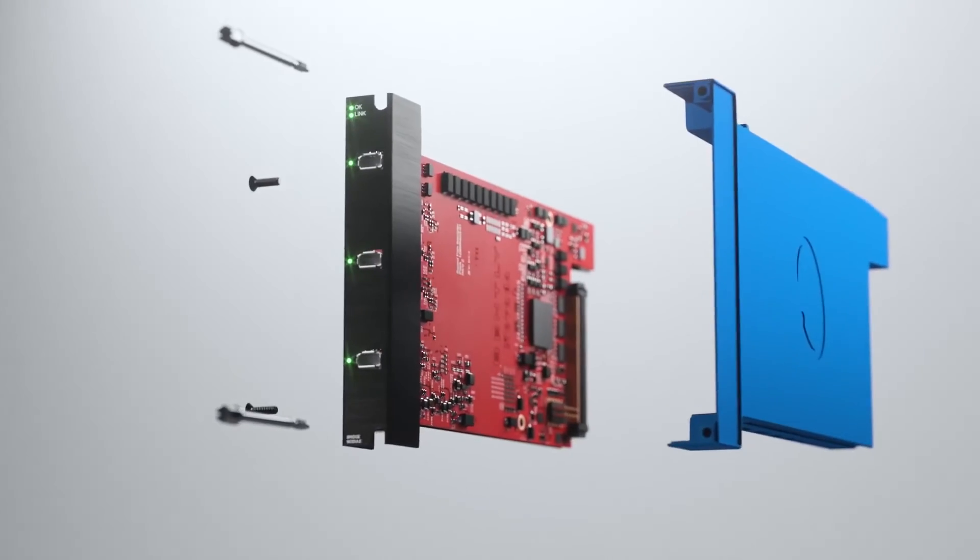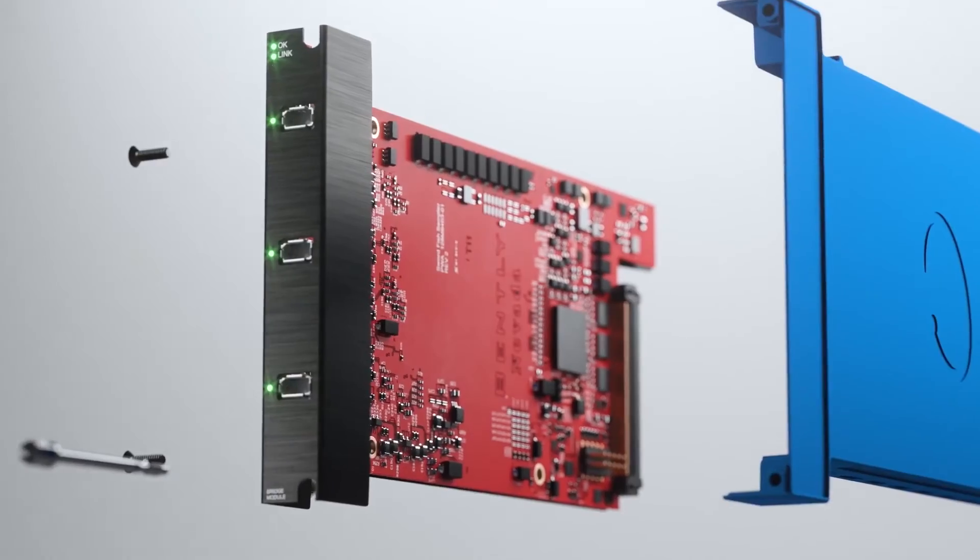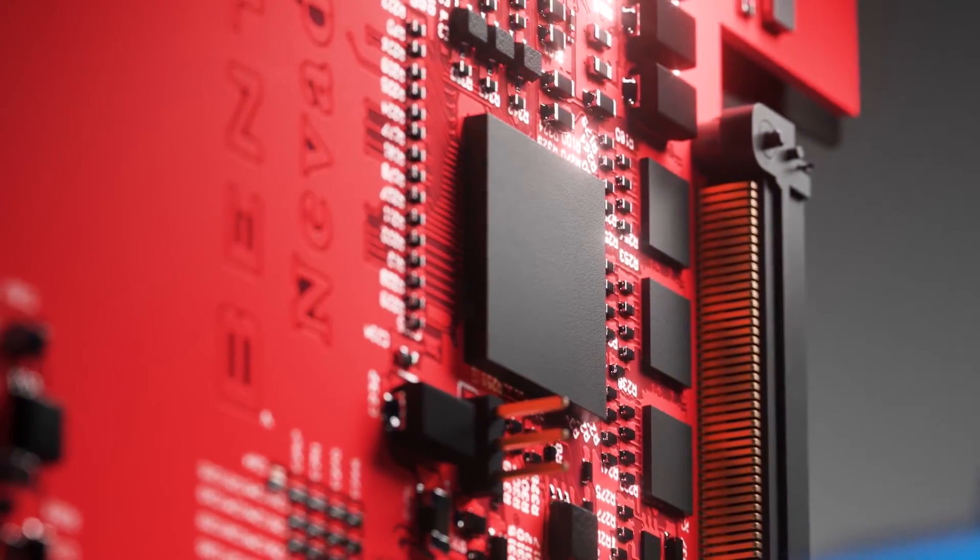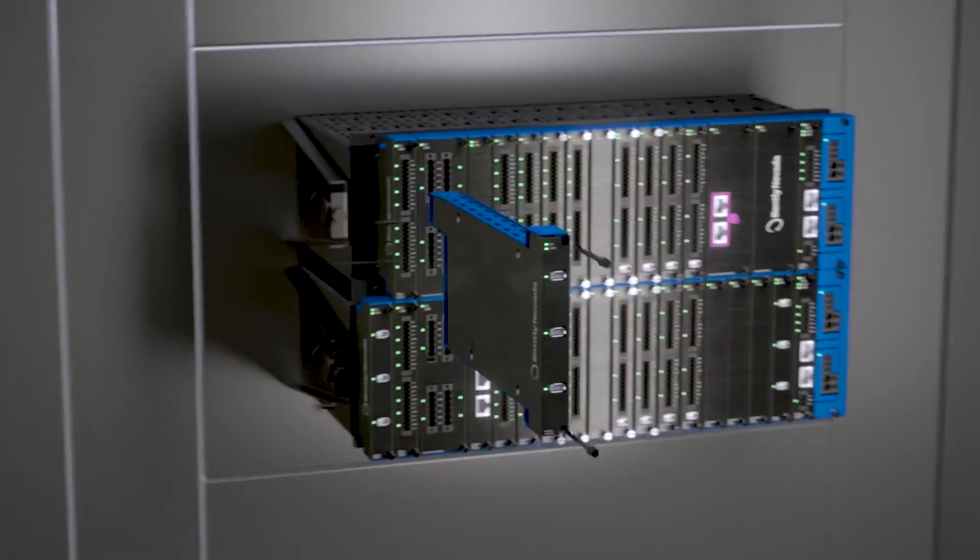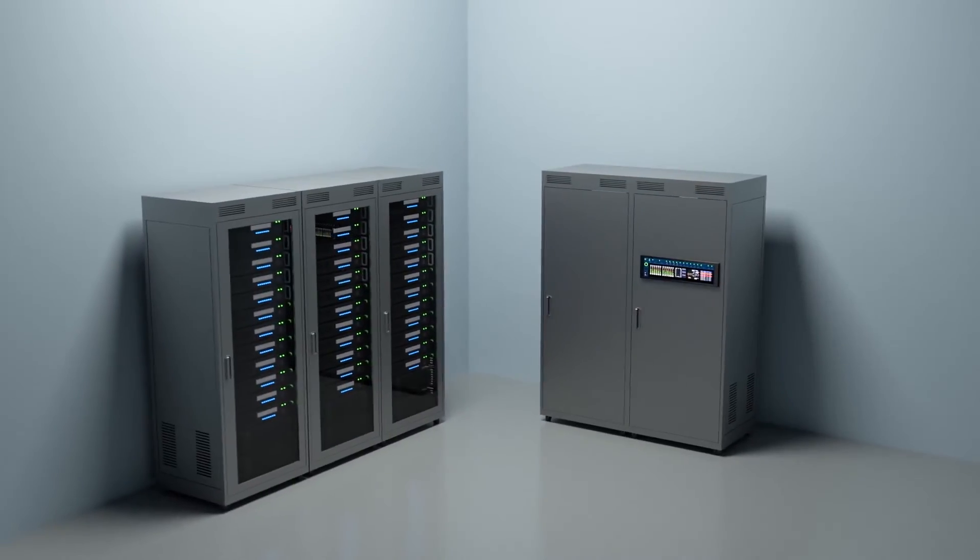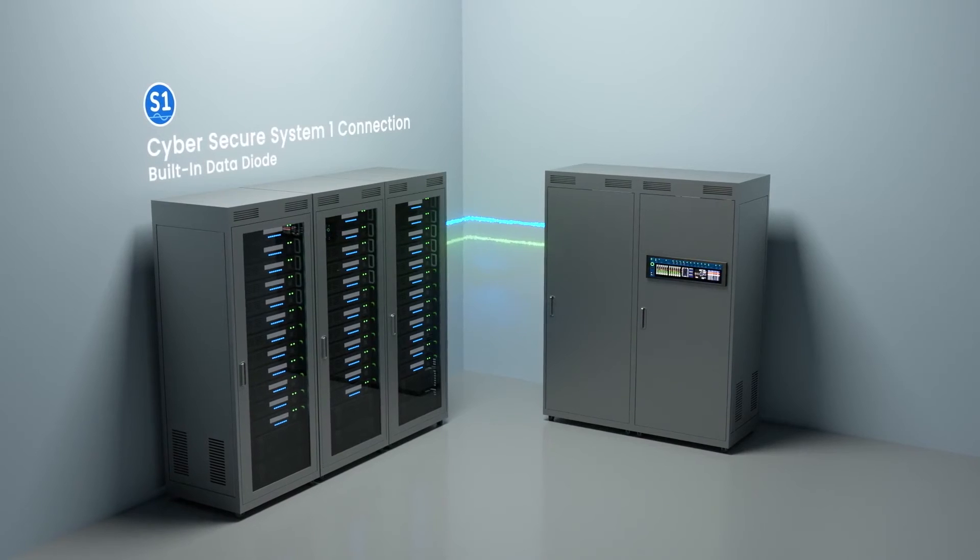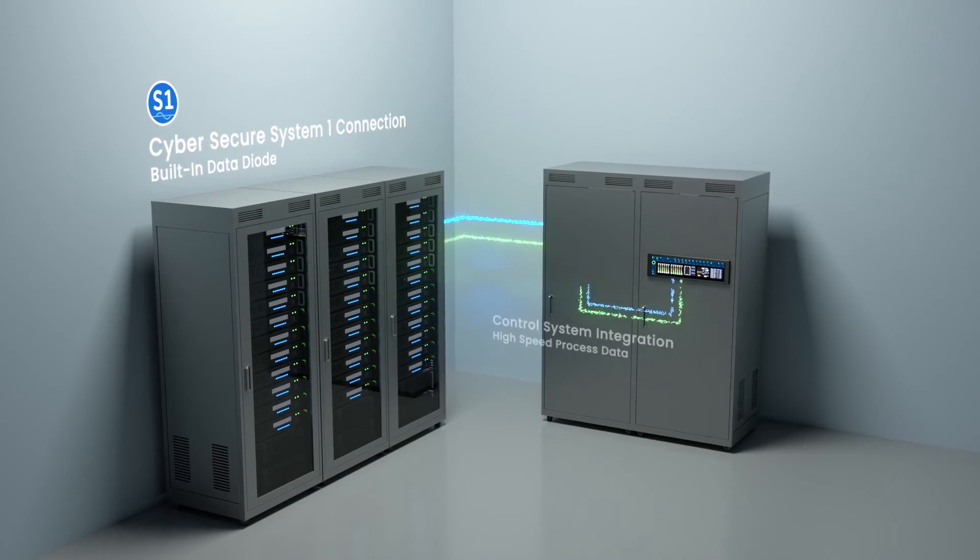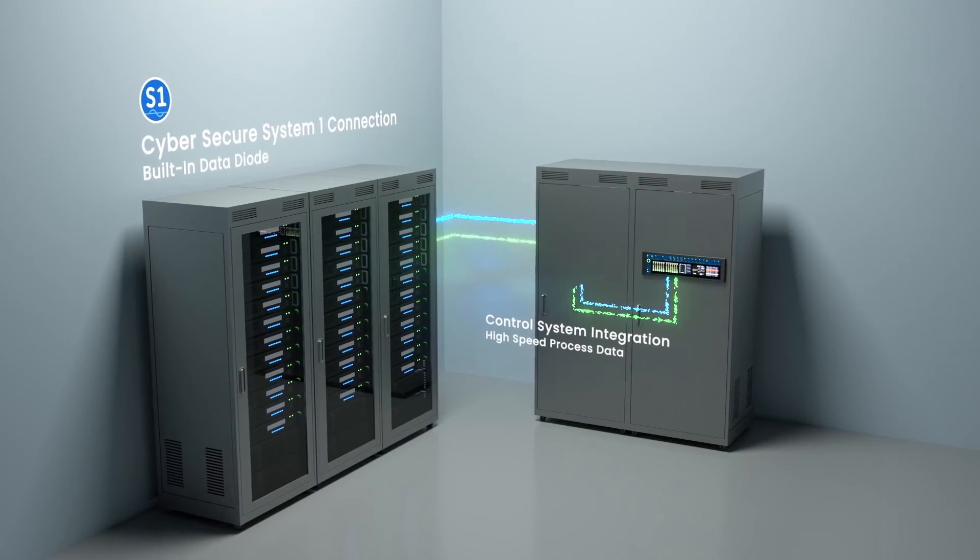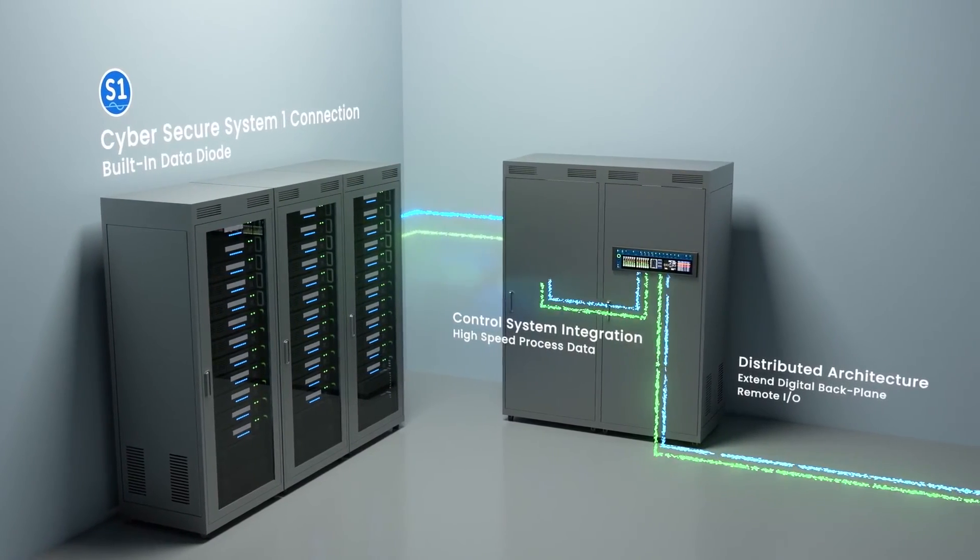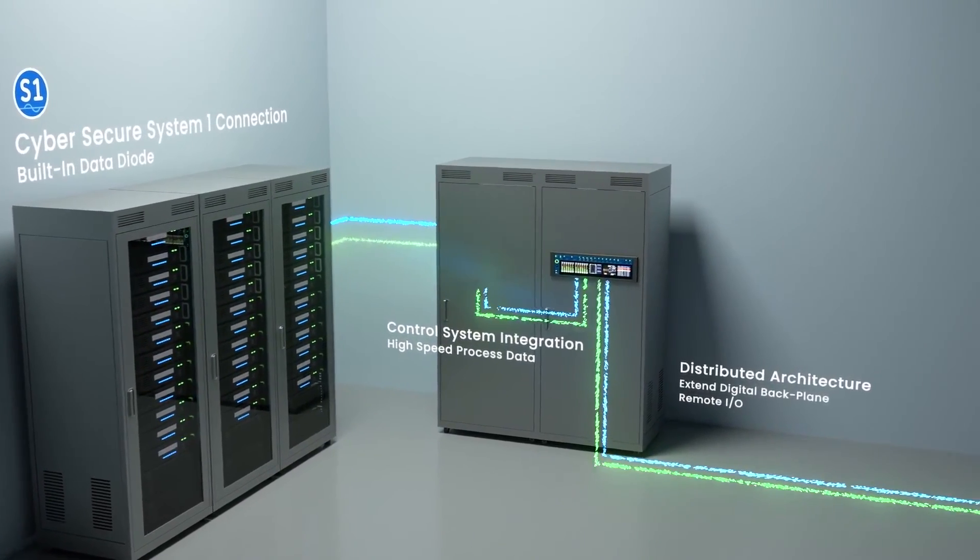As you mentioned earlier around the condition monitoring approach versus the protection approach, we really wanted the system to be flexible for both options. If I want to deploy this system for just plant-wide type assets or fans that you don't need to do protection on, you can configure the system with a single protection processor. If you have a protection application, we can put many more protection processors in there to achieve redundancy.